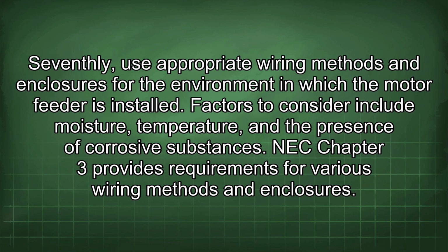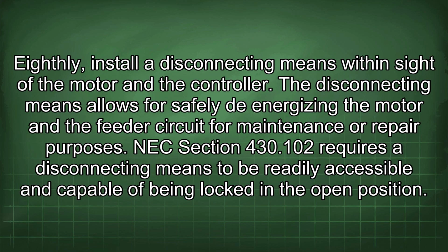Seventhly, use appropriate wiring methods and enclosures for the environment in which the motor feeder is installed. Factors to consider include moisture, temperature, and the presence of corrosive substances. NEC Chapter 3 provides requirements for various wiring methods and enclosures. Eighthly, install a disconnecting means within sight of the motor and the controller. The disconnecting means allows for safely de-energizing the motor and the feeder circuit for maintenance or repair purposes. NEC section 430.102 requires a disconnecting means to be readily accessible and capable of being locked in the open position.